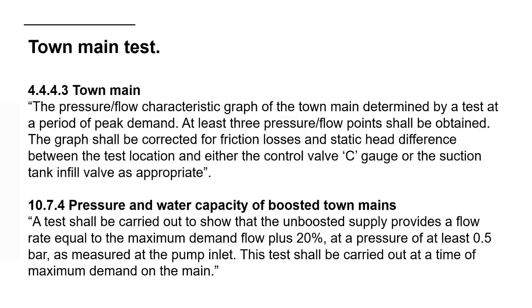Then we can make that decision. There's also 10.7.4, which is talking about a slightly different test where you have a boosted town main supply. I'm going to talk about boosted town main supply a little bit more later on in the presentation. But here it's a very similar test, where we need maximum demand flow plus 20%. So we want additional flow. And for the pressure, we basically just need half a bar. As long as we've got half a bar of pressure on the town main, then we're happy.